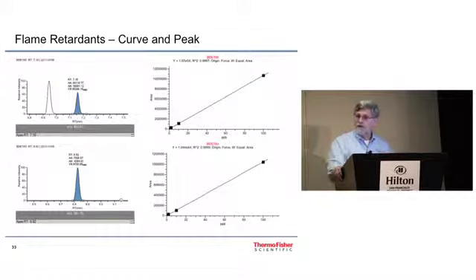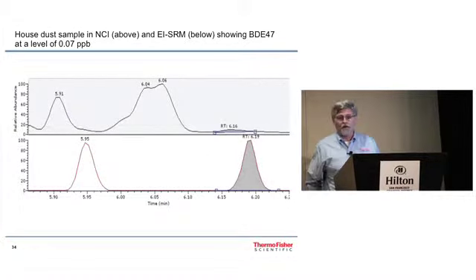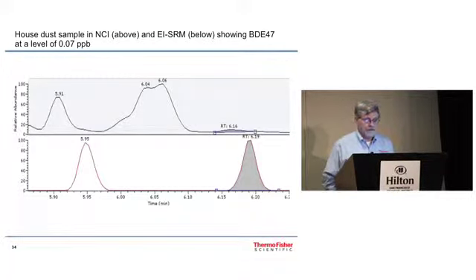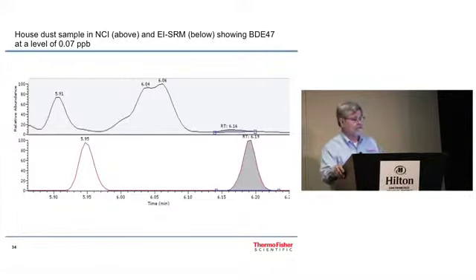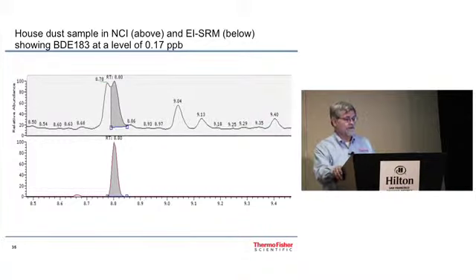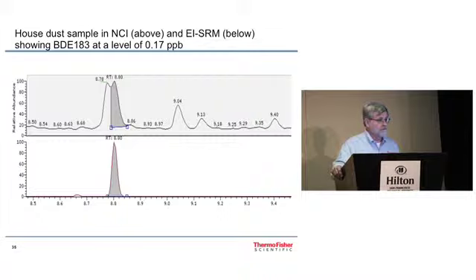Flame retardants, just going to show you a little bit on flame retardants. Peak shapes, curves for 100 and 183. Now most people are running single quad NCI to look at flame retardants. And this is an example comparing a single quad on the top with the triple quad on the bottom in EI SRM mode. And this is BDE 47 at 0.07 PPB. And you notice there's a big difference in peak shape. Here's another example of house dust, 183 at 0.17 PPB. The top being the single quad in NCI. And the bottom one EI on the triple quad. Again, it shows you the selectivity of the instrument.